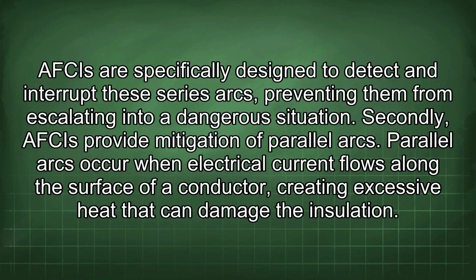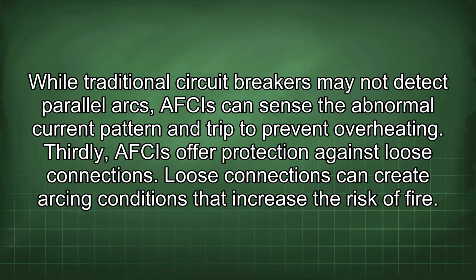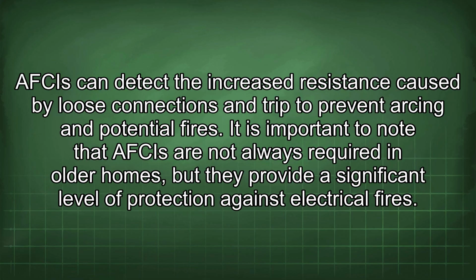Secondly, AFCIs provide mitigation of parallel arcs. Parallel arcs occur when electrical current flows along the surface of a conductor, creating excessive heat that can damage the insulation. While traditional circuit breakers may not detect parallel arcs, AFCIs can sense the abnormal current pattern and trip to prevent overheating. Thirdly, AFCIs offer protection against loose connections. Loose connections can create arcing conditions that increase the risk of fire. AFCIs can detect the increased resistance caused by loose connections and trip to prevent arcing and potential fires.